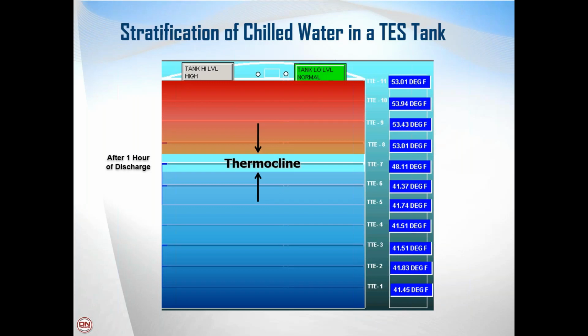And then there's the typical sensors that you would have in any central plant system, where you would be measuring chill water flow rate through pipes, temperatures in pipes, valve positions, and so those types of instrumentation that are typically in a central plant would also be used in a thermal energy storage type system.